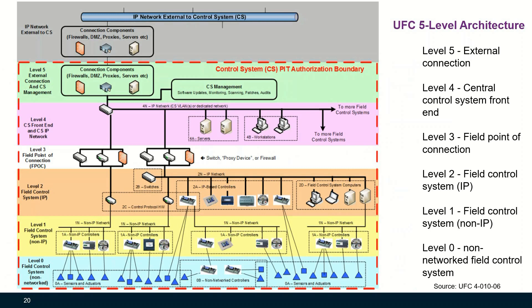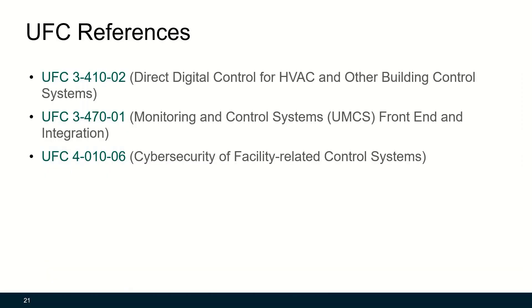Here is another representation of the UFC five-level HVAC system architecture. Level zero is basically inputs and outputs. Level 1N (non-IP network) is the field control network. Level 2N (IP network) is the building controls network. Level three is a switch or firewall. Level four includes BAS servers and workstations. Everything within the dotted red line is part of the building control system. Several UFC references are listed if you want to learn more about building automation system architecture.